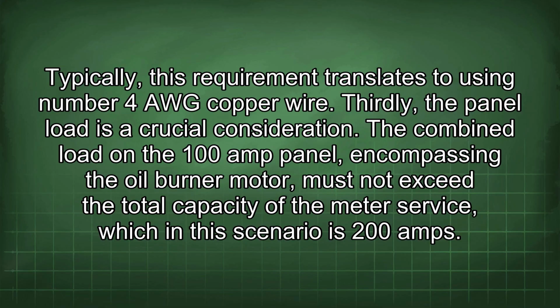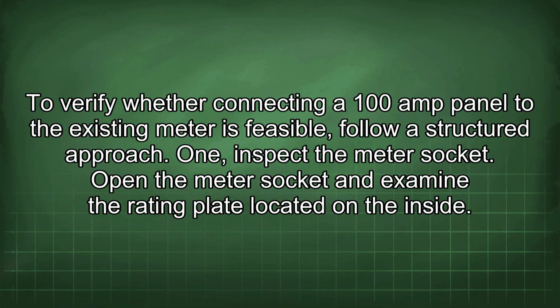Thirdly, the panel load is a crucial consideration. The combined load on the 100 amp panel, encompassing the oil burner motor, must not exceed the total capacity of the meter service, which in this scenario is 200 amps. To verify whether connecting a 100 amp panel to the existing meter is feasible, follow a structured approach.